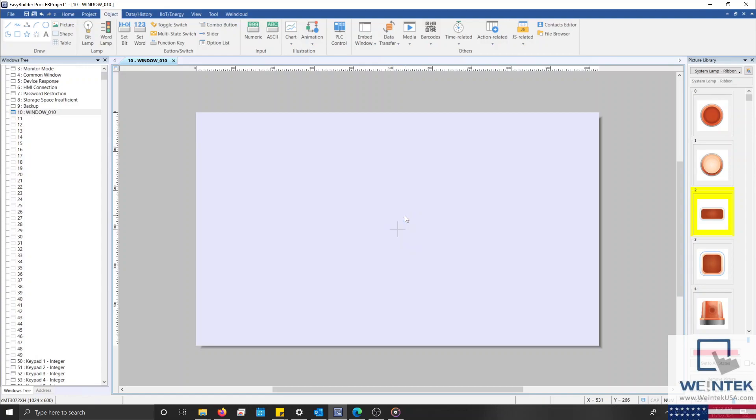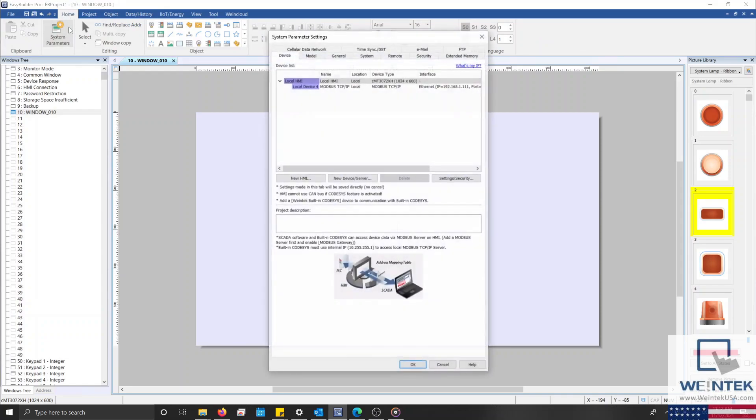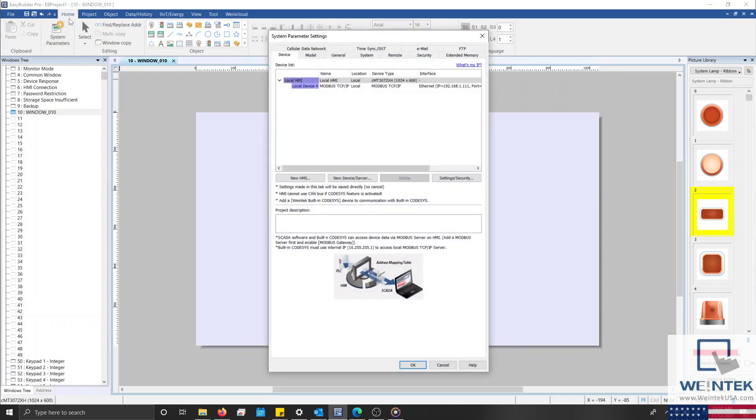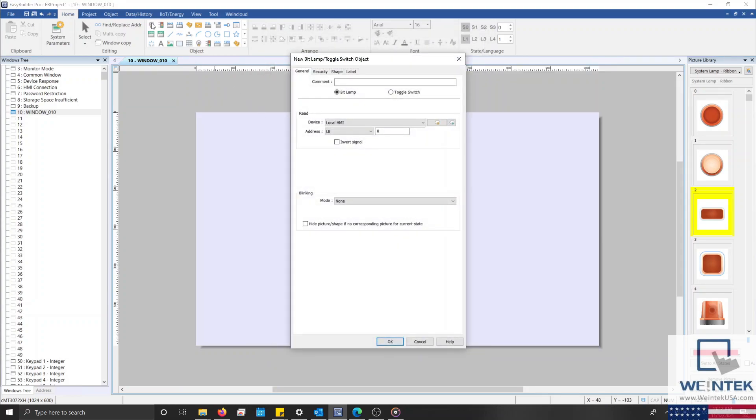In order to address an object to an external device, you'll need to add the driver for that device within the System parameters. The System parameters can be accessed within the Home tab. For most objects, the Read and Write address can be configured within the General tab, which can be found within the Objects Properties menu.